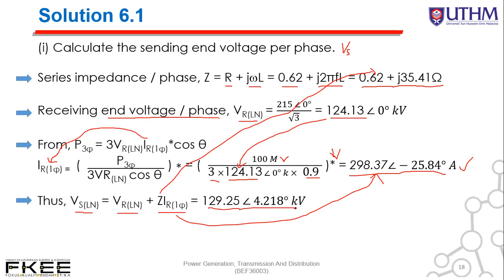Now, determine voltage regulation and efficiency of the transmission line. The voltage at the receiving end under no load is equal to the voltage at the sending end. Line to line equal to square root of 3 times Vs line to neutral single phase. So we got square root of 3 times 129.25, that is 223.87 kilovolt. Sorry, this is the voltage at the receiving end under no load.